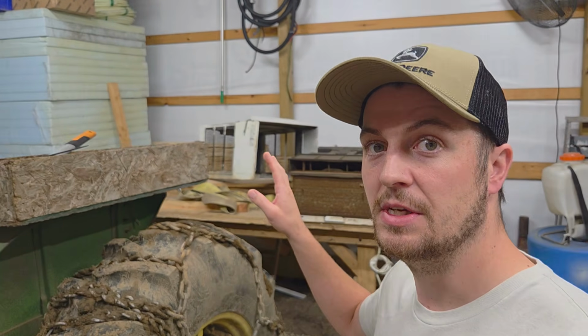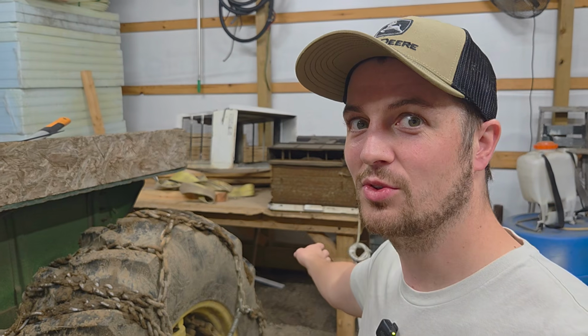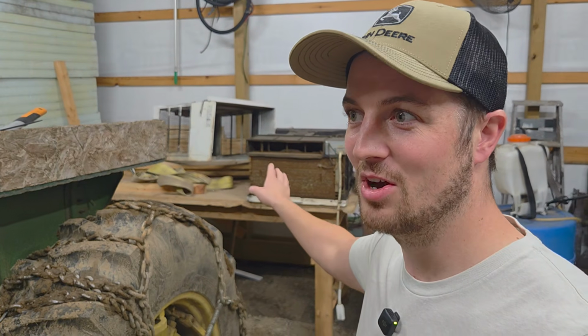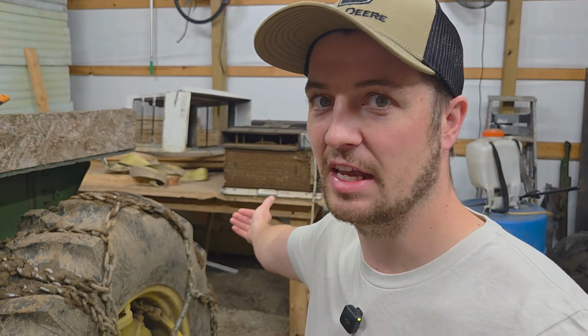One last thing that I think is an advantage of this is because it's a ground source unit and there's not a big fan running, I'm actually going to be increasing the efficiency of this unit and increasing the output of it, rather than if the back end of the window air conditioner is hanging outside. So yes, it's a 14,000 BTU system, but maybe I'll be closer to that 1.5 tons or maybe even more with it being a ground source unit.